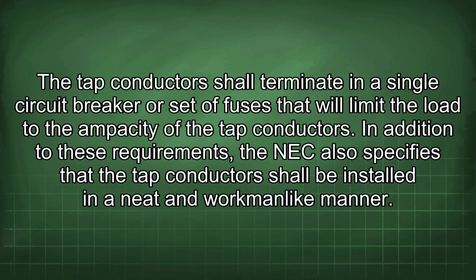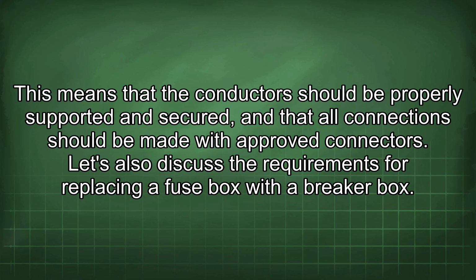In addition to these requirements, the NEC also specifies that the tap conductors shall be installed in a neat and workmanlike manner. This means that the conductors should be properly supported and secured, and that all connections should be made with approved connectors. Let's also discuss the requirements for replacing a fuse box with a breaker box.